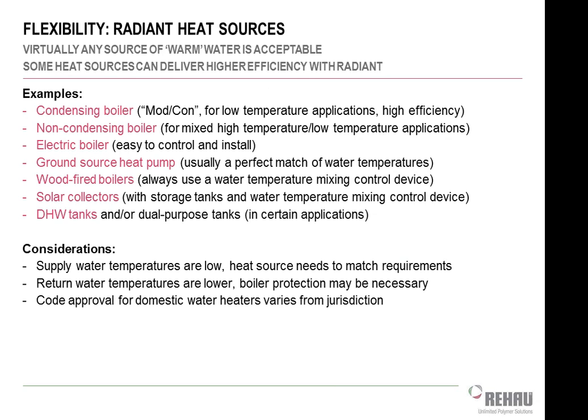So a non-condensing boiler would be a cast iron or steel boiler or a copper boiler. And if I allow those boilers to have lower temperatures, it'll cause condensation, and that condensation will eat a hole in those ferrous metal heat exchangers. A condensing boiler, by contrast, will have a stainless steel heat exchanger or titanium or copper nickel or something like that, aluminum, a non-ferrous metal that can handle that condensate. So condensing boilers can handle lower return water temperatures and enjoy the extra energy benefits of that condensate. So they lend themselves very well to radiant systems.